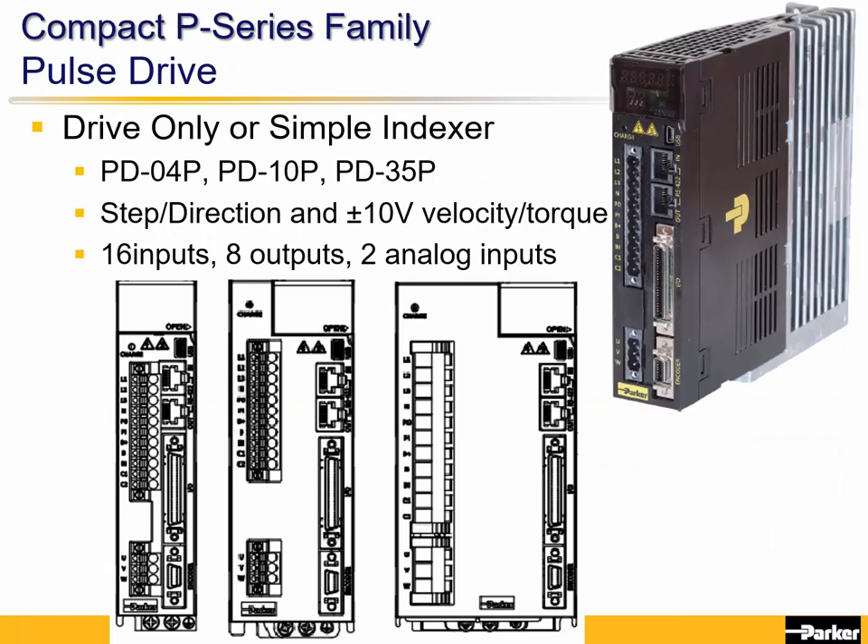The P-Series Indexer drive can be configured as a base drive to be driven from a step and direction signal, or plus or minus 10 volt analog torque or velocity modes with encoder feedback for the controller. It can also be set up as a simple indexer with different moves stored within it and selected from PLC inputs. It also has Modbus and can be controlled that way.